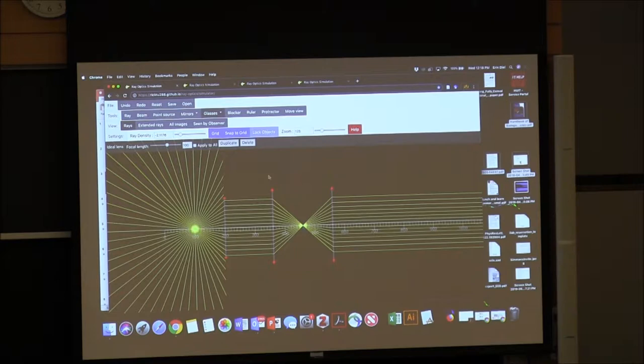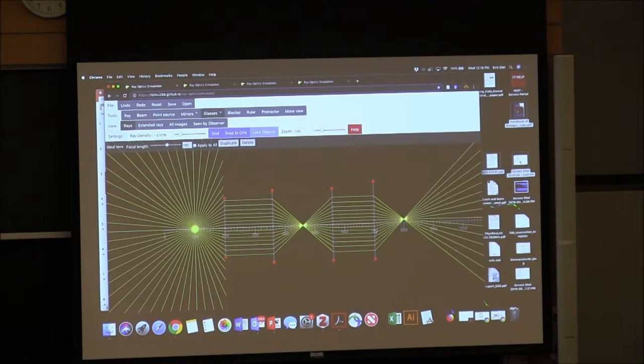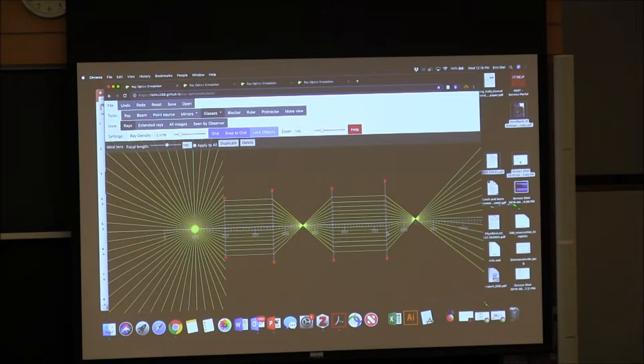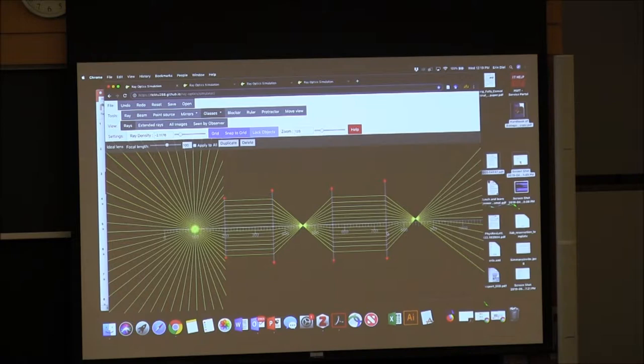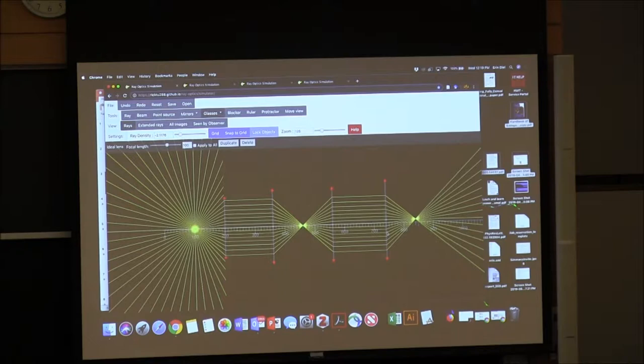In a microscope you could have a series of these lenses, and there would be points on either side called conjugate planes. Let's say this is our very small jellyfish that we're imaging. At some points we have parallel rays — no image — but where rays converge to a point again we get an image of our sample. Then again another image. These conjugate planes contain the same information, and you could form an image at each of them. This is important to think about when building a system with multiple overlapping light paths.